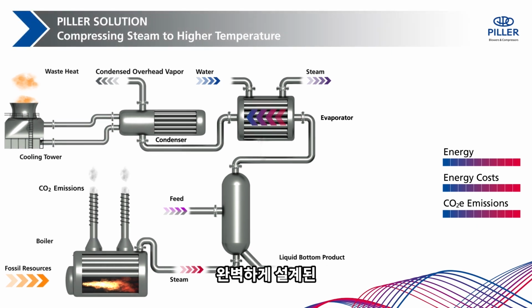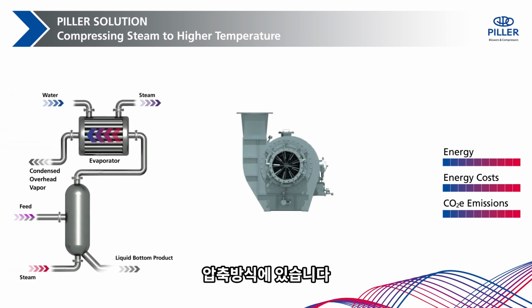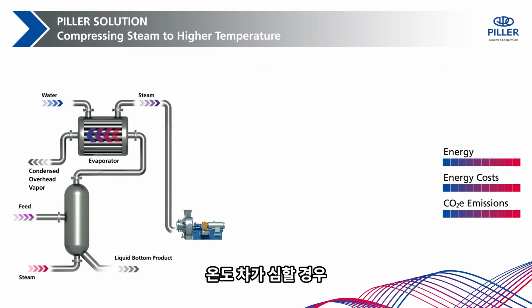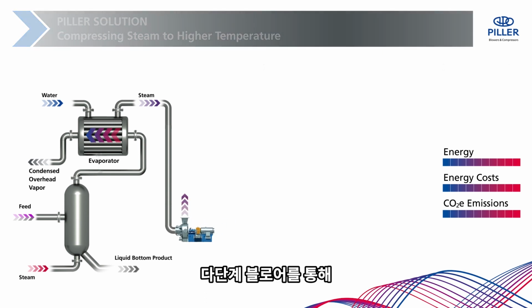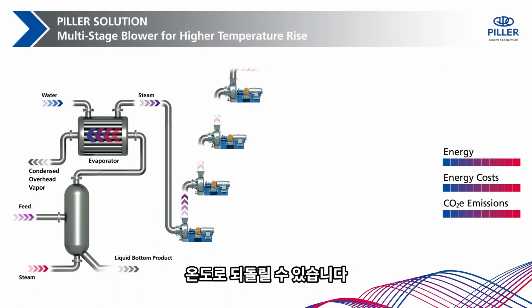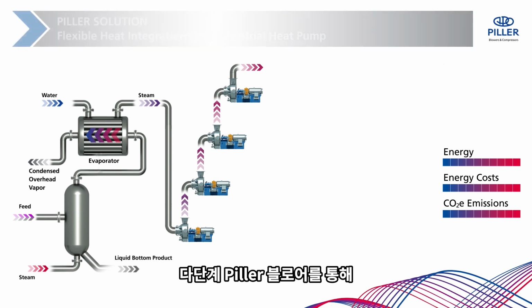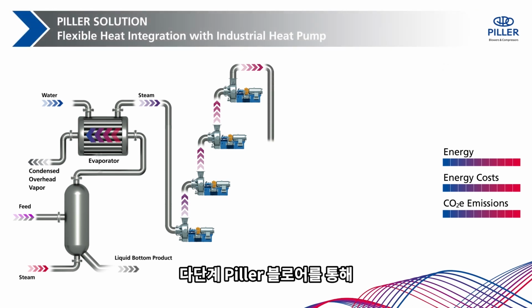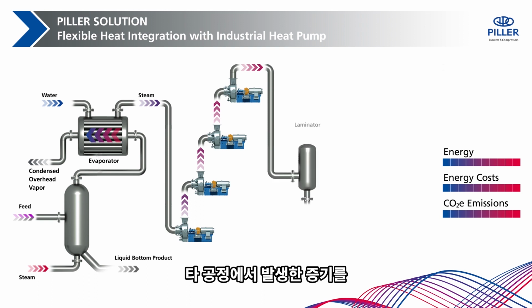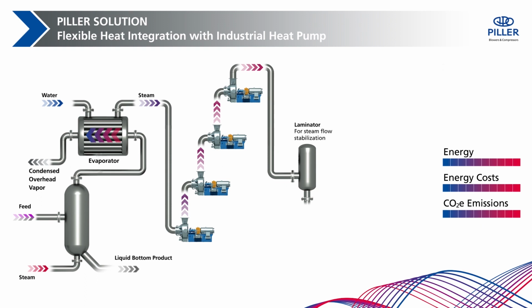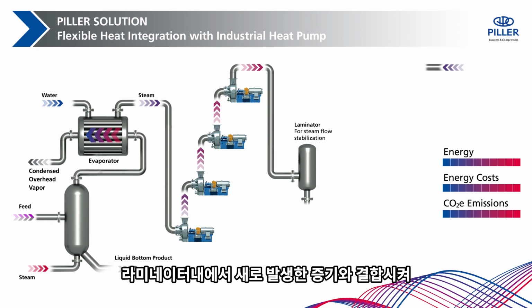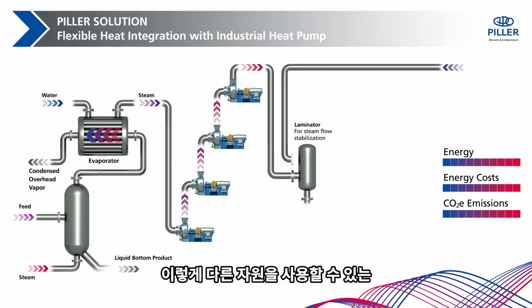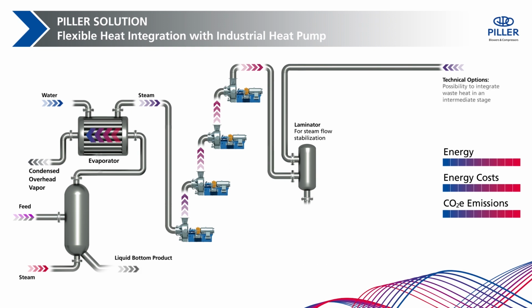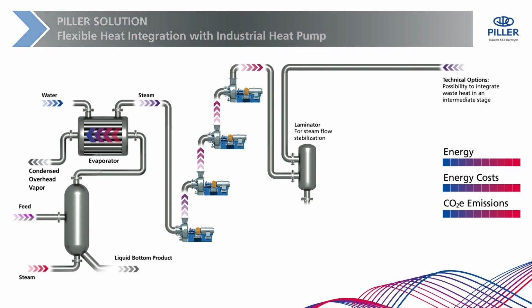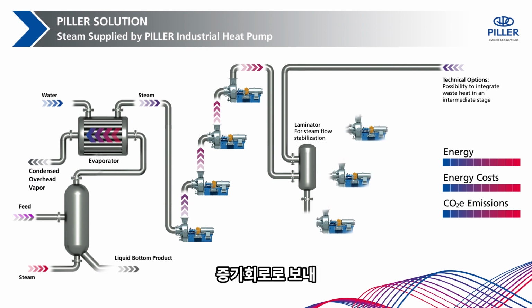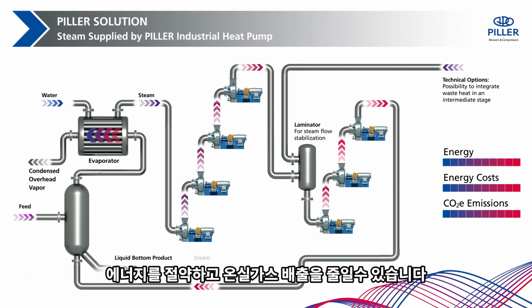The system's core is the compression with our perfectly engineered PILLER high-performance blowers. For high temperature differences, a multi-stage blower system lifts the waste heat from low temperature back to a usable temperature while preserving the heat of vaporization. The multi-stage arrangement of PILLER blowers opens the system to integrate additional waste heat sources. Excess steam, like flash vapor from other processes, can be combined with the freshly generated steam in a laminator. This flexibility of integrating other sources at any intermediate stage allows even more heat recovery. Feeding back the compressed vapor into your process or into a steam network will preserve energy and reduce greenhouse gas emissions.